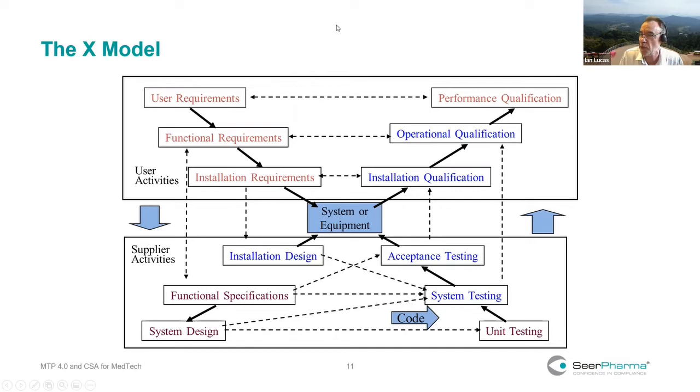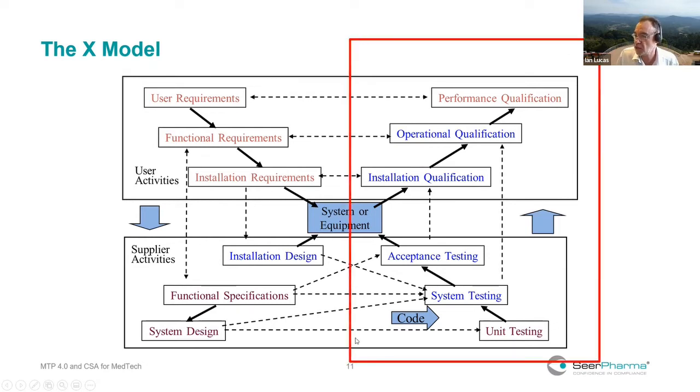On the top of this, you would have a validation plan. On the bottom of this, you would have a validation report. And then for each one of your systems, this is a worst case situation where you do different levels of testing. At the end of the day, as I said, this functional requirements is what the system has to do. The design is how the system has to do it. This whole thing here is called validation. This whole right-hand side here is called testing. And this whole top box over here is called qualification.